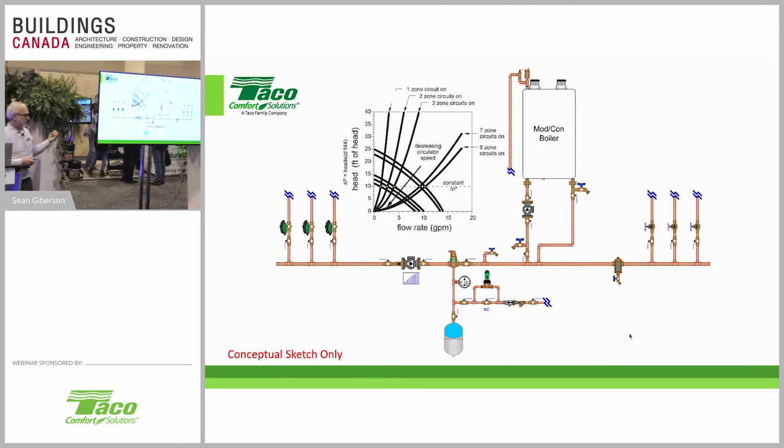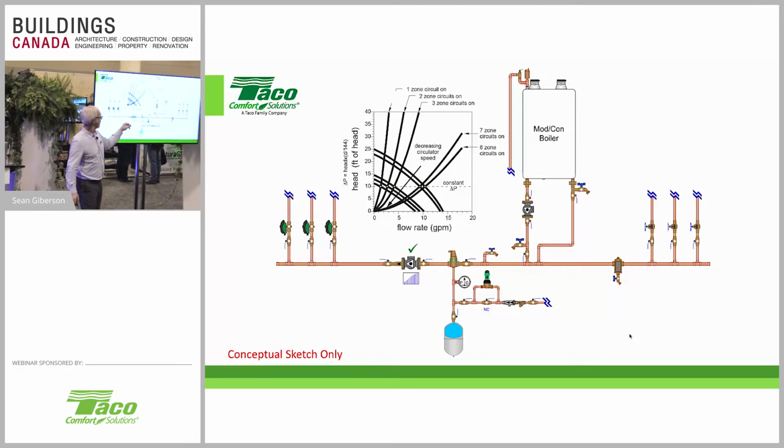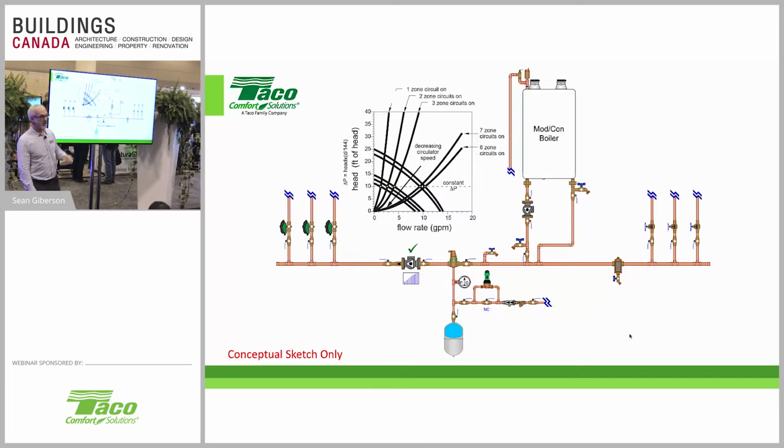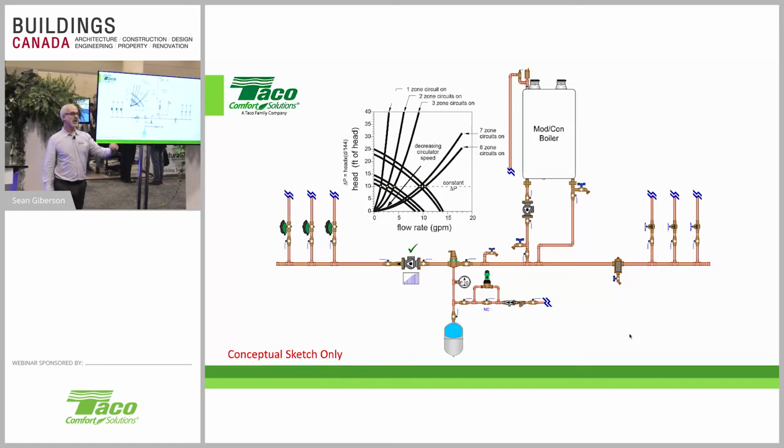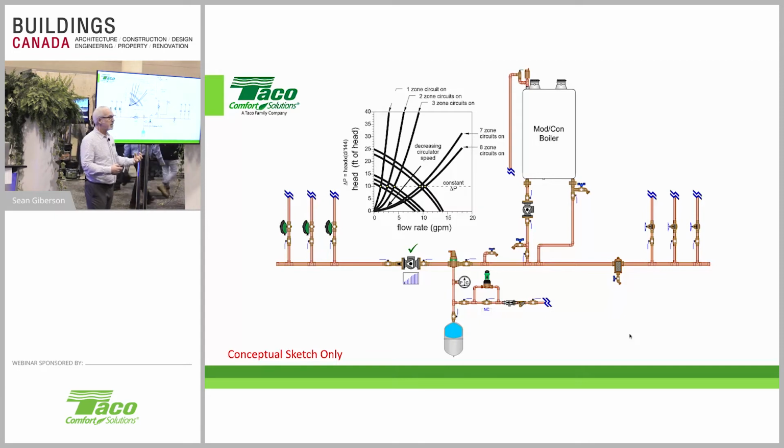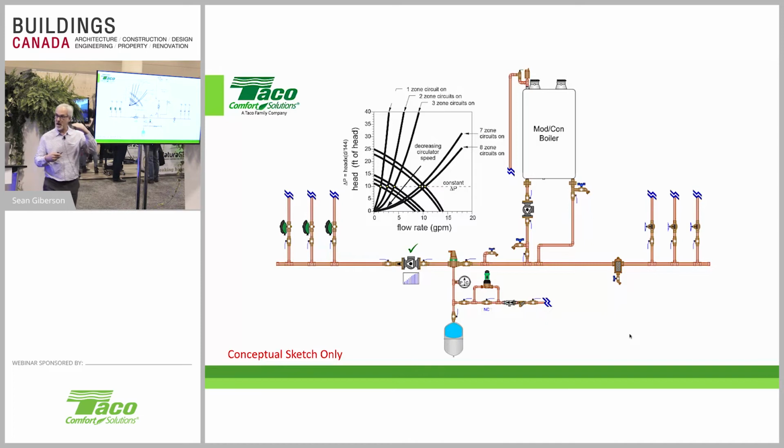Where we go next, we'll skip through just a couple here. So basically what we've said is, variable speed works really good on that secondary type of system. When we talk about boilers and what really makes them tick, most manufacturers say, we want a fixed speed through that. Don't play with our modulation. Give us fixed speed, let us figure out how the boiler modulates. We have to respect that. We'll work with them. I would say in most cases, we'll go with fixed speed.